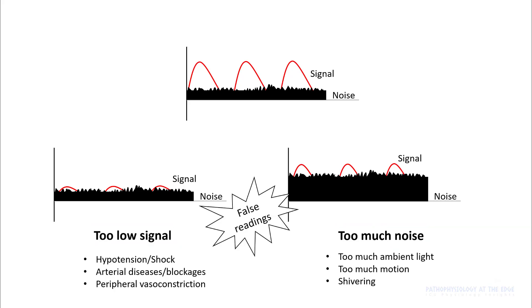The main problem with pulse oximetry is your signal-to-noise ratio. If you have too low a signal or too much noise, you can get false readings. Too low signals can be seen in hypotension, peripheral artery disease, blocks, and peripheral vasoconstriction. You can have too much noise if there is shivering, too much motion, or too much ambient light.